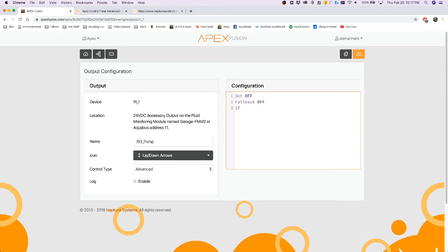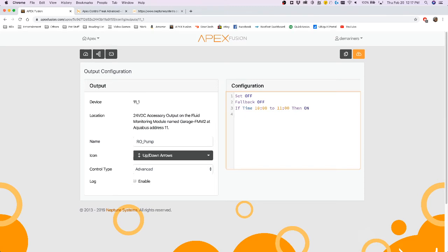Now if you were to put an if statement here, so if time 10 a.m. to 11 a.m., then on, the time will override the set off because it is lower on the list here.